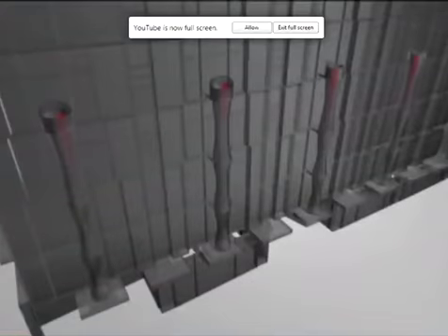CH2 does not use conventional technology to cool the building. Whereas conventional buildings use air, CH2 uses water. It cools its water passively by lowering water through 15 metres on 5 shower towers on the southern facade of the building. That water is taken at 13 degrees down to the basement, where it's stored in 3 large tanks.